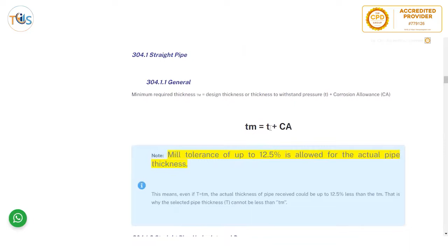So TM equal to T, which is the design thickness plus corrosion allowance. Now we have a mill tolerance of up to 12.5% allowed for the actual pipe thickness. That's a lot of allowance. This means that if T equals TM, the overall thickness, then the actual thickness of pipe received could be up to 12.5% less than the TM. That is why the selected pipe thickness cannot be less than TM.